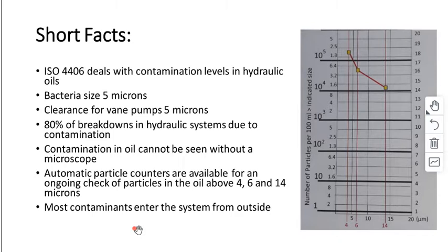80% of breakdowns in hydraulic systems are due to contamination, as we mentioned before. Contamination in oil cannot be seen without a microscope. And automatic particle counters are available for an ongoing check of particles in the oil above 4, 6, and 14 microns. Remember when we looked at those figures? Let me just go back to this slide.